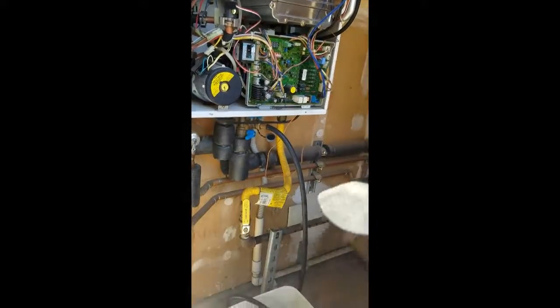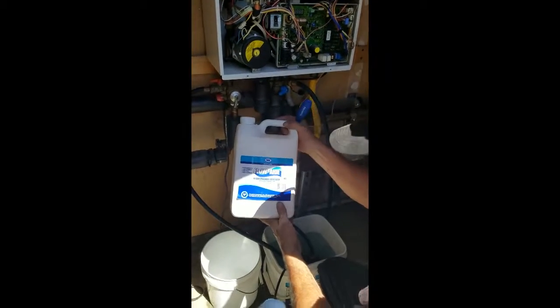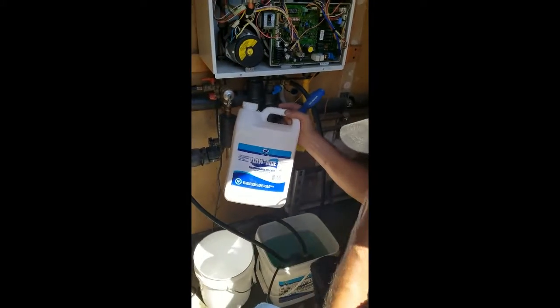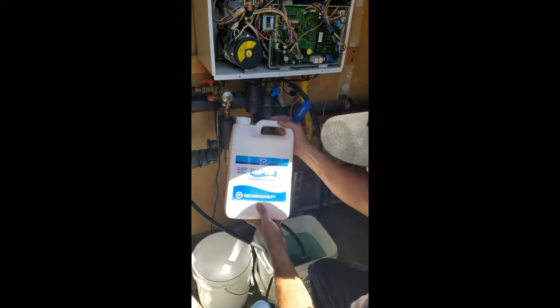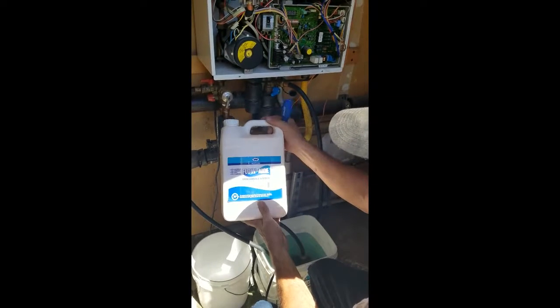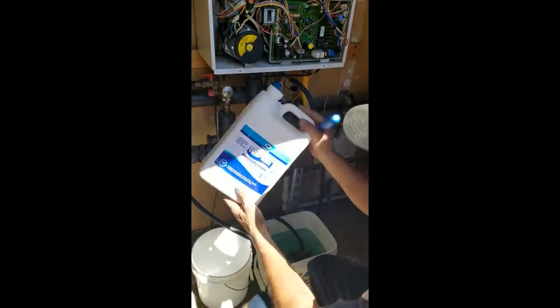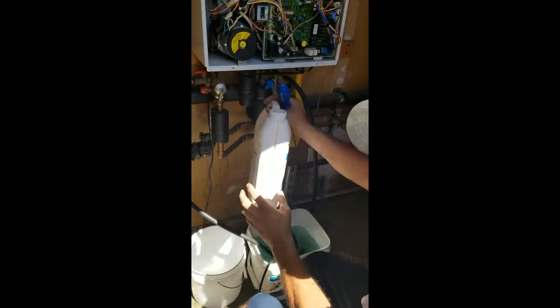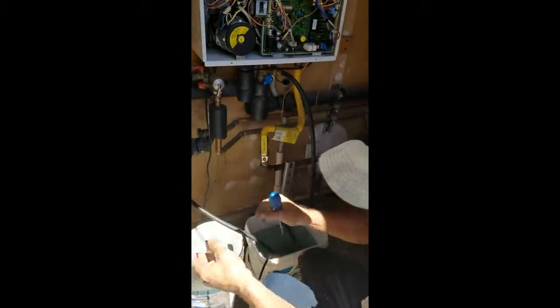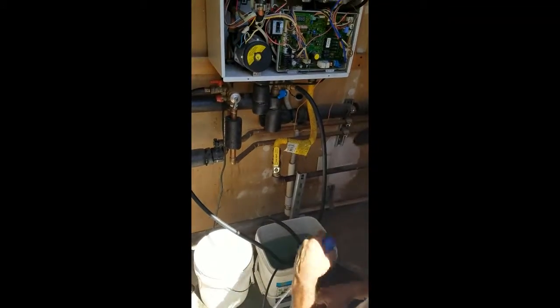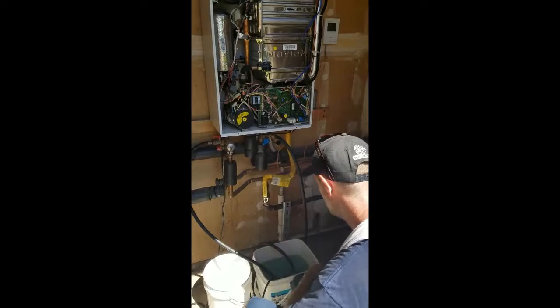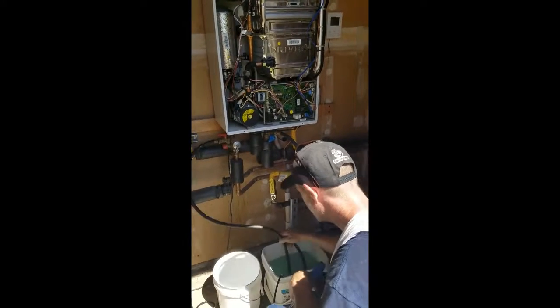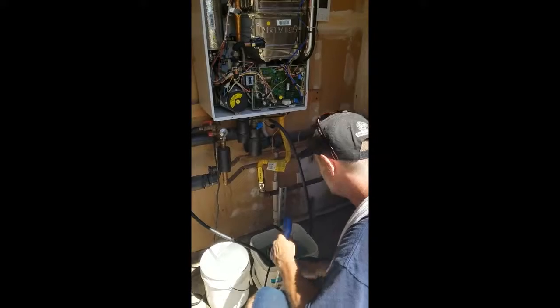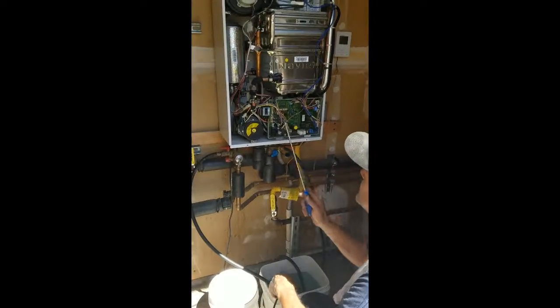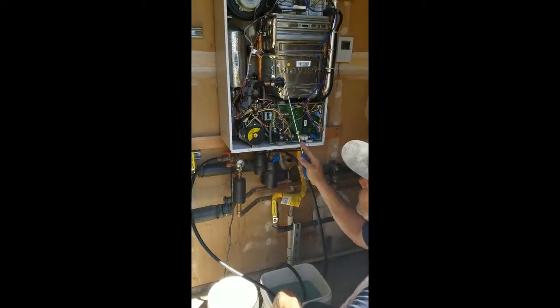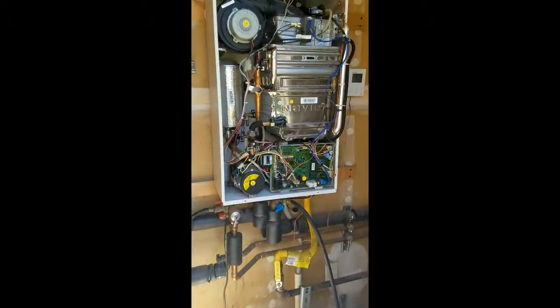We like to use flow aid. You'll see a lot of videos where people are using vinegar, which is all right, but there's no science to your mixture. This is pre-calculated, shake it really well, and you get 4 quarts out of here. It takes 1 quart to flush a unit, and you want to flush it for about 45 minutes, then back flush it to make sure you're not leaving any foreign objects inside the unit, which would cause flow restrictions through the flow sensors.